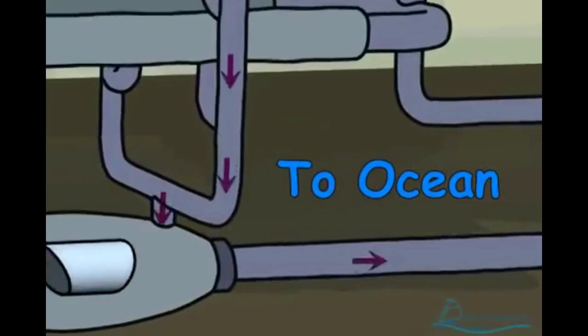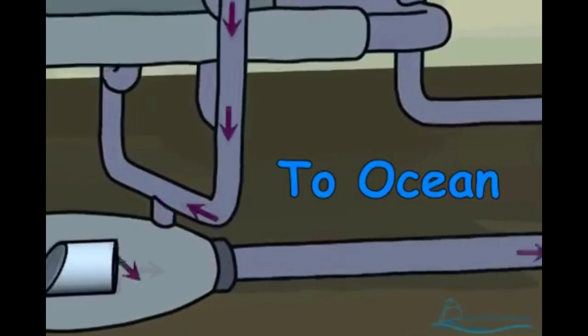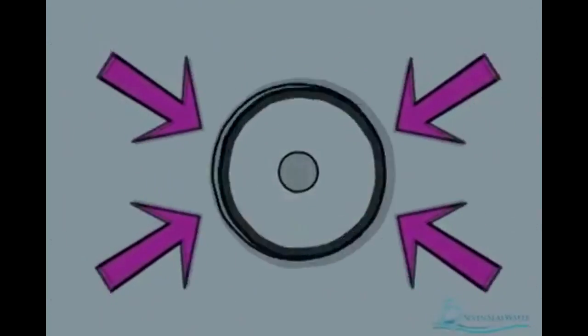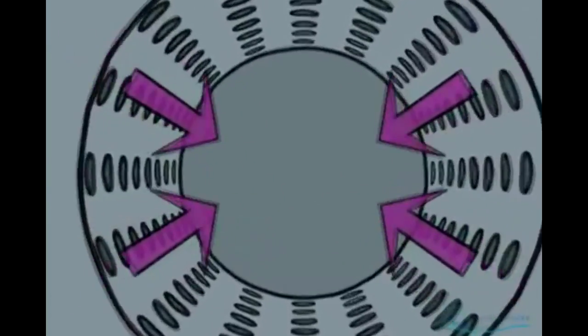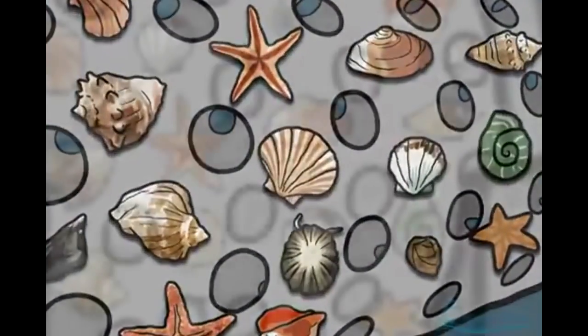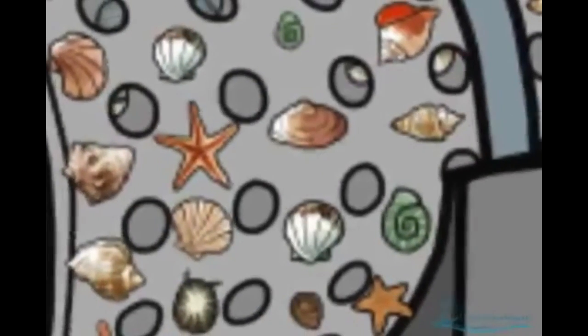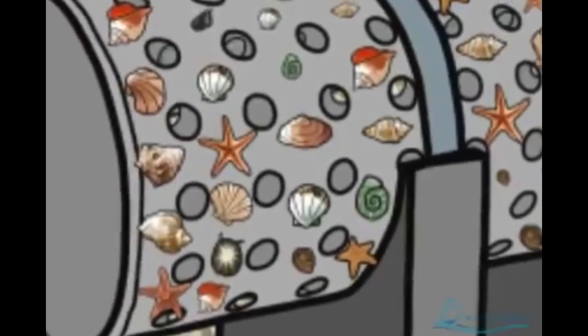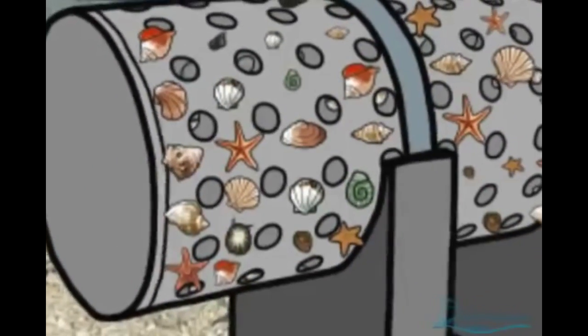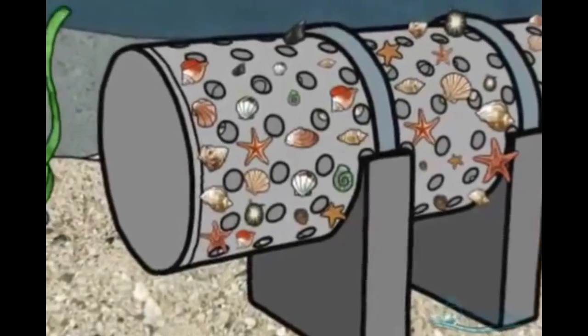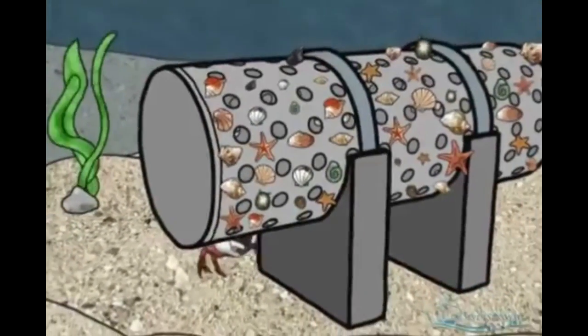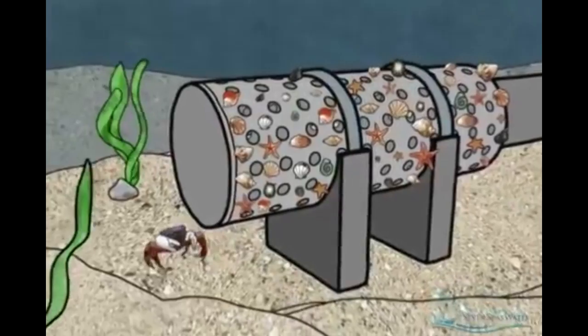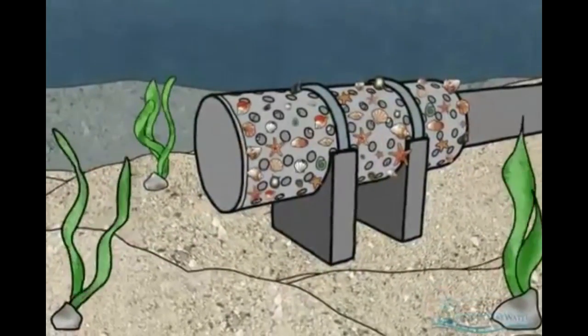The concentrated salt stream will have about a 60% higher salinity than the incoming seawater. It is sent back to the ocean through a brine disposal well or a device known as a brine outfall. The brine outfall is situated in an area of significant ocean flow so that the salt levels are quickly returned to equilibrium with the ocean. The location for the outfall should contain no sensitive marine ecosystems. In a properly designed brine outfall, no noticeable increase in salinity can be detected at a distance of a few meters from the discharge.